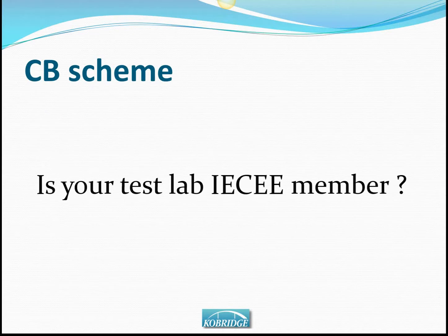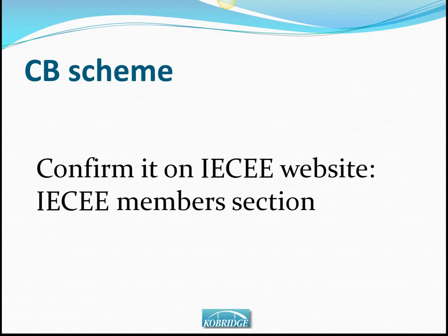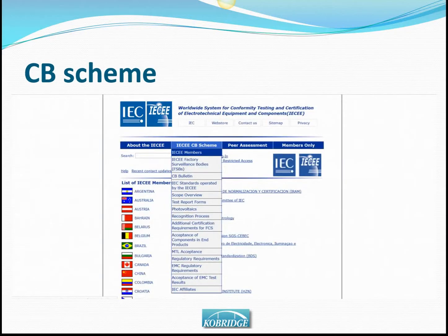Now, is the test lab an IEC member? That's a very, very important question. It has to be confirmed on the IEC-EE website in the IEC members section. We find it here with this screenshot with the IEC CB scheme.